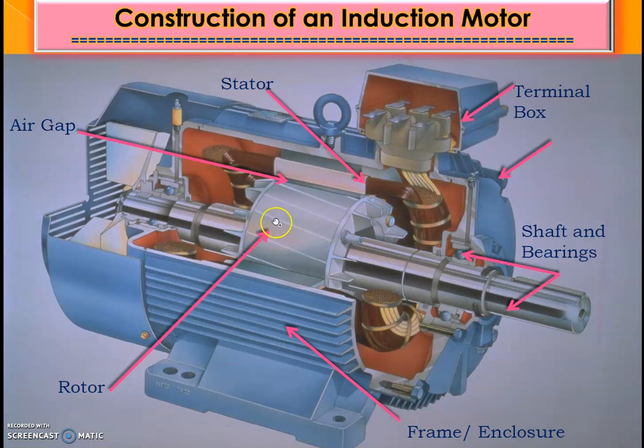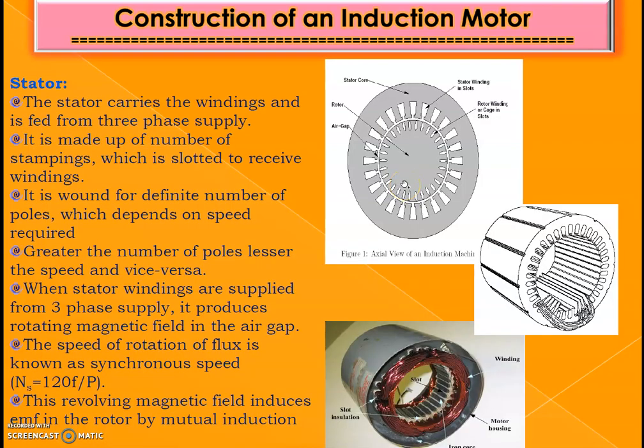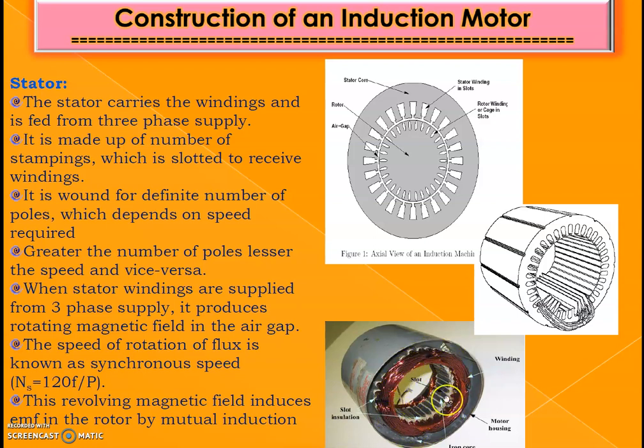In the terminal box, all stator terminals are accessible. Since this is a squirrel cage machine, there are no external rotor terminals. The stator carries the winding which is fed from three-phase supply. Inside the stator slots, the winding is constructed — this is how the winding is placed inside the stator slots. Each slot has insulation, and the enamel-coated winding is wound for a fixed number of poles — it may be a two-pole or four-pole machine.